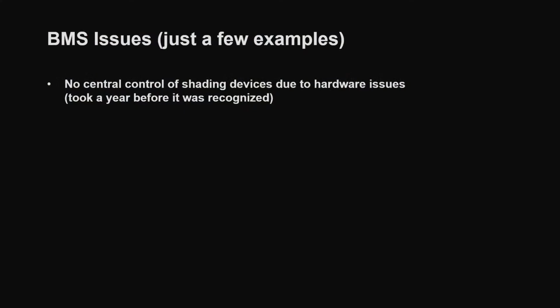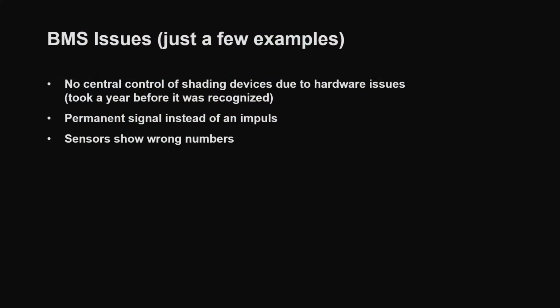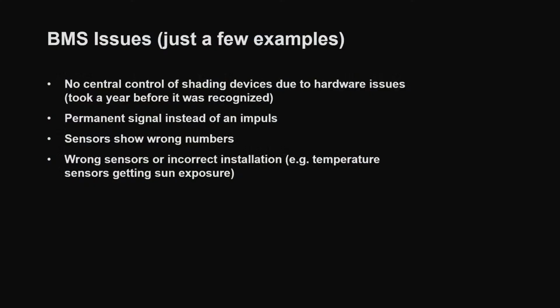We had several control issues in this building, just to list some: no central control of shading devices due to hardware issues, which took them a year to even recognize—a year just to notice the shading didn't go up and down when it should. There was a permanent signal instead of an impulse. Sensors showed wrong numbers, so you needed to check every single sensor. Wrong sensors or incorrect installation, like temperature sensors getting sun exposure, gave wrong readings. Some sensors' positions got lost—nobody knew where they were.